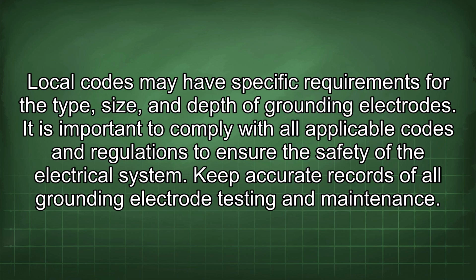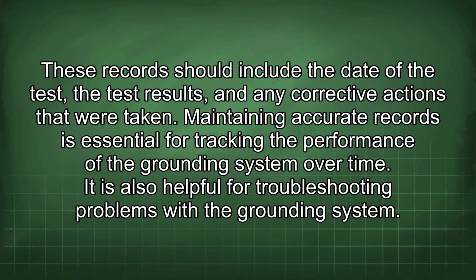Keep accurate records of all grounding electrode testing and maintenance. These records should include the date of the test, the results, and any corrective actions that were taken. Maintaining accurate records is essential for tracking the performance of the grounding system over time. It is also helpful for troubleshooting problems with the grounding system.